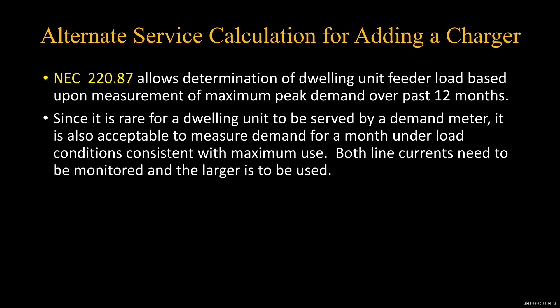That is, put a recording ammeter on both of the two hotlines coming in and measure the current that's coming, and then find out which one peaked out at the maximum value over that month. And you can use that then as your load. Actually, you have to add 125% of that. But then you compare your measurement with your calculation from 220.83, and maybe you don't have to upgrade your service after all. So you try them both.